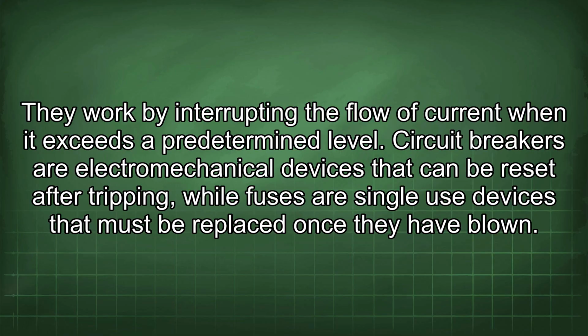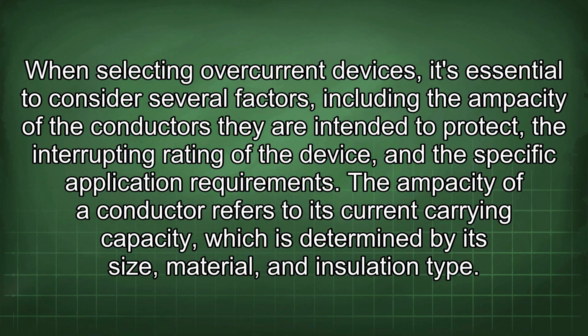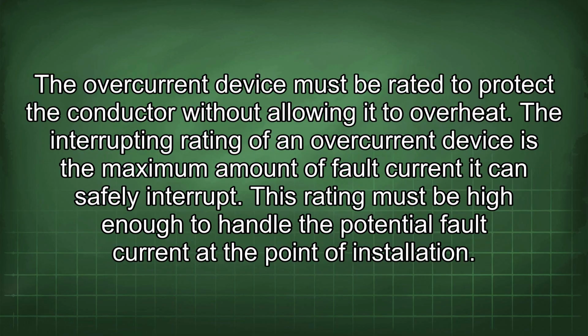When selecting overcurrent devices, it's essential to consider several factors, including the ampacity of the conductors they are intended to protect, the interrupting rating of the device, and the specific application requirements. The ampacity of a conductor refers to its current carrying capacity, which is determined by its size, material, and insulation type. The overcurrent device must be rated to protect the conductor without allowing it to overheat. The interrupting rating of an overcurrent device is the maximum amount of fault current it can safely interrupt. This rating must be high enough to handle the potential fault current at the point of installation.